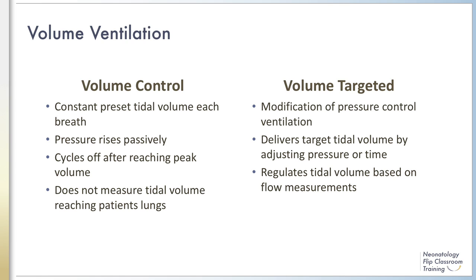In contrast, volume targeted ventilation is actually a modification of pressure control ventilation using a flow sensor to measure tidal volume at the proximal airway. Volume targeted ventilation is designed to deliver a targeted tidal volume by adjusting the ventilator pressure and time. These devices regulate tidal volume based on the measurement of gas flow rate — the higher the flow rate, the shorter the inspiratory time. Flow and thus tidal volume can be measured either during inhalation or exhalation.